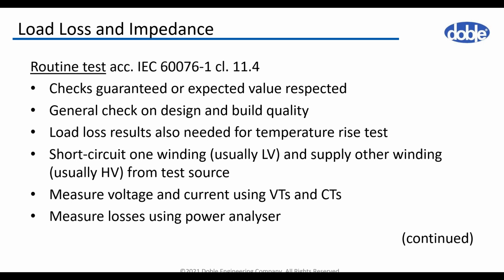Transformer load loss and impedance is the first test which we will review. It's a routine test as per IEC 76 Part 1, and it is defined in item 11.4 of the standard. The purpose of the test is to verify whether the load loss and impedance agree with the guaranteed and expected results. The results are important not just for capitalization of the losses, but also for the safe operation of the unit. Comparison with calculated values gives us an indication about the design and build quality, and also about eddy losses due to the leakage flux in steel parts. In addition, it is important to know impedance and load loss to carry out the temperature rise test as well.